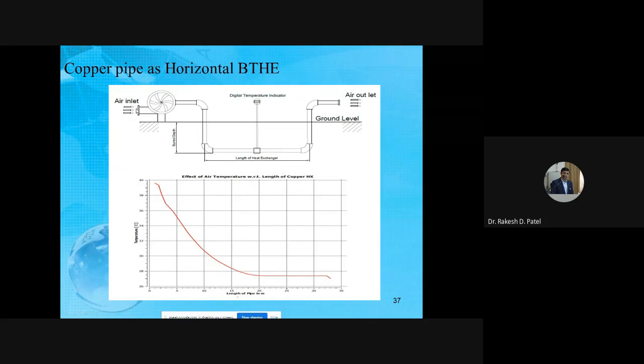The air inlet is at ambient condition through this blower, and air passes through this heat exchanger, which is buried at a certain depth. The length of the heat exchanger is approximately 24 to 25 meters, and the conditioned air is outletted from the heat exchanger at the ground level and passes into the building or room. This graph shows the temperature with respect to the length of the pipe. From this graph, the air temperature is approximately 40 degrees centigrade at the inlet condition, and at the outlet of the heat exchanger it is approximately 25 degrees centigrade.